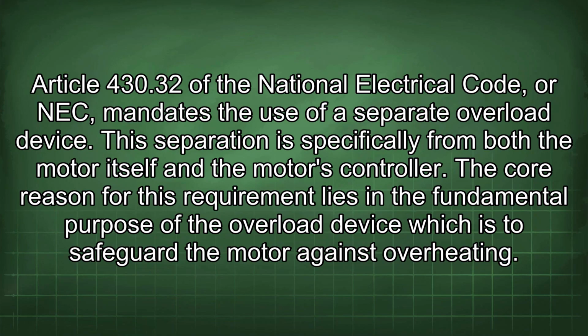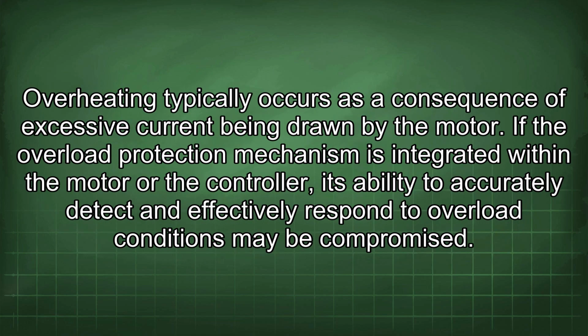Article 430.32 of the National Electrical Code, or NEC, mandates the use of a separate overload device. This separation is specifically from both the motor itself and the motor's controller. The core reason for this requirement lies in the fundamental purpose of the overload device, which is to safeguard the motor against overheating. Overheating typically occurs as a consequence of excessive current being drawn by the motor. If the overload protection mechanism is integrated within the motor or the controller, its ability to accurately detect and effectively respond to overload conditions may be compromised.